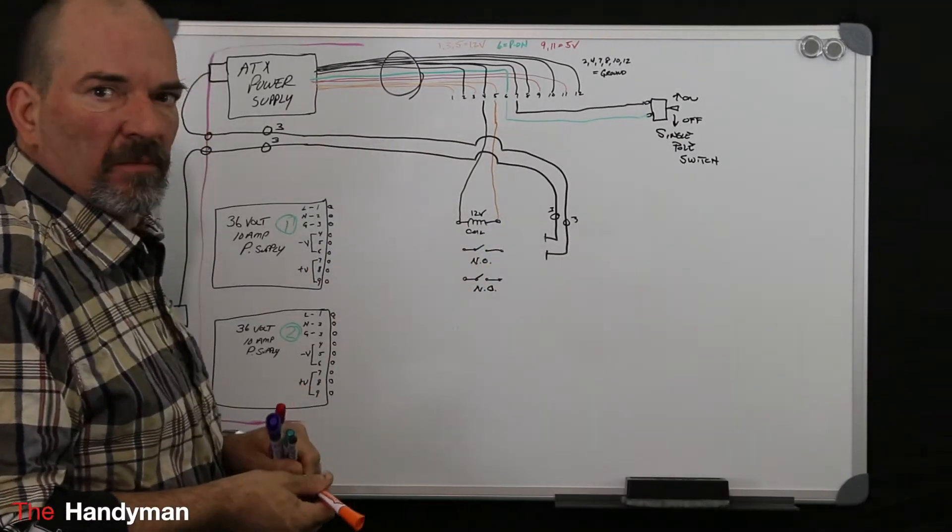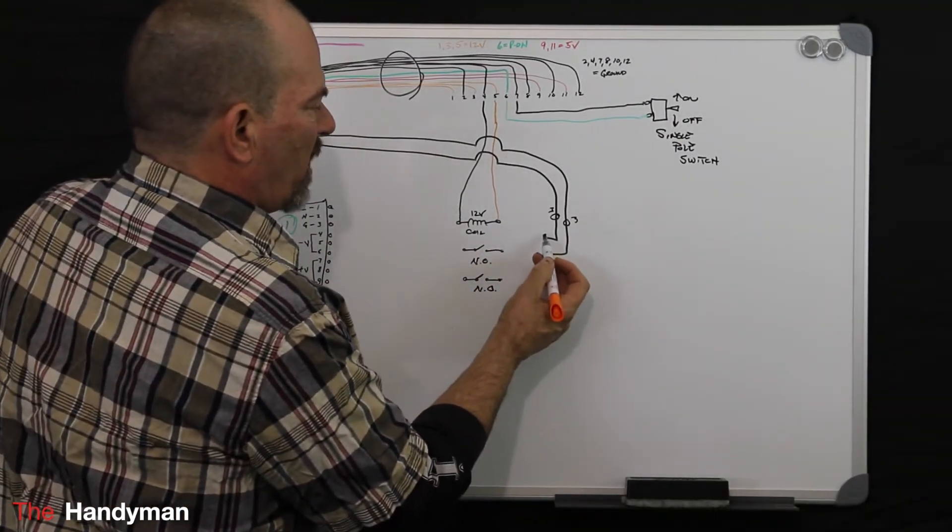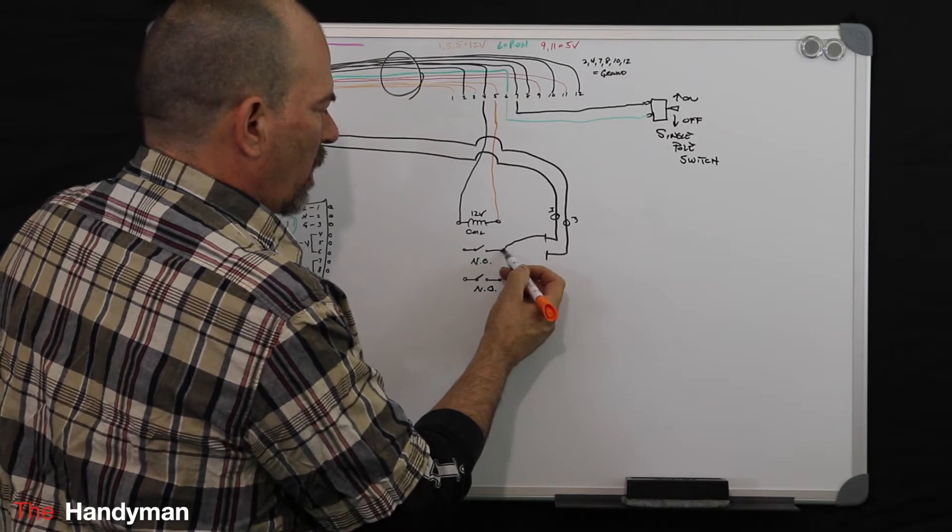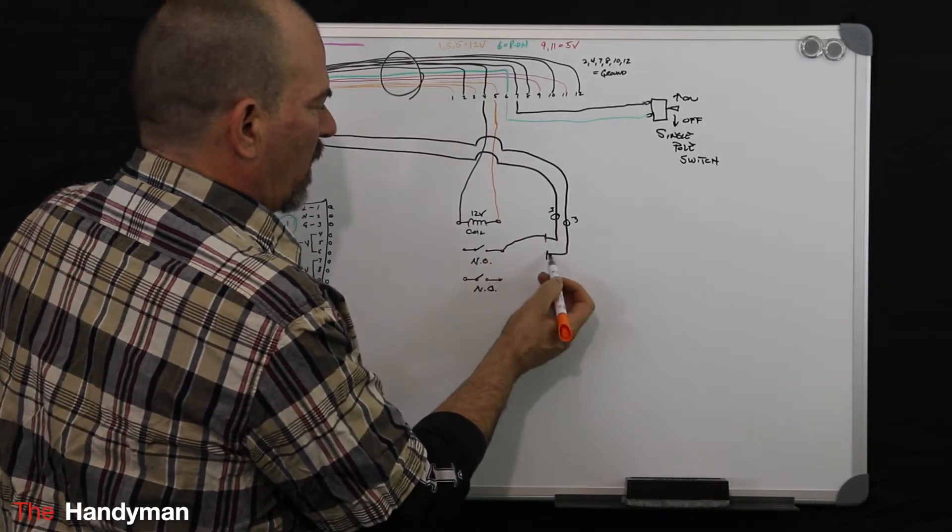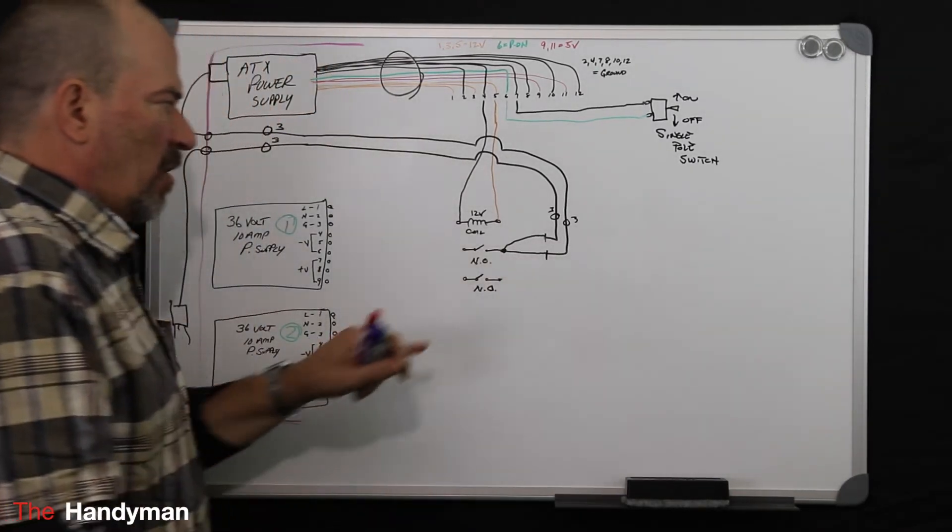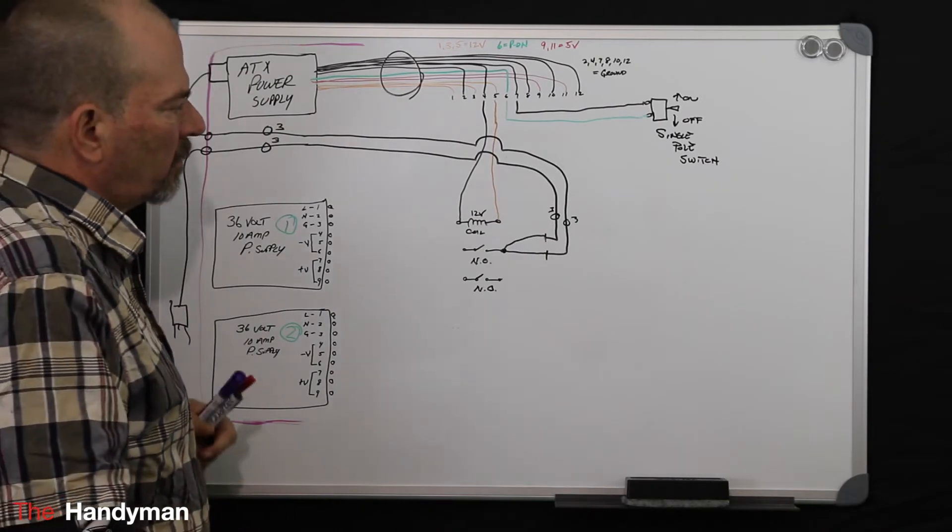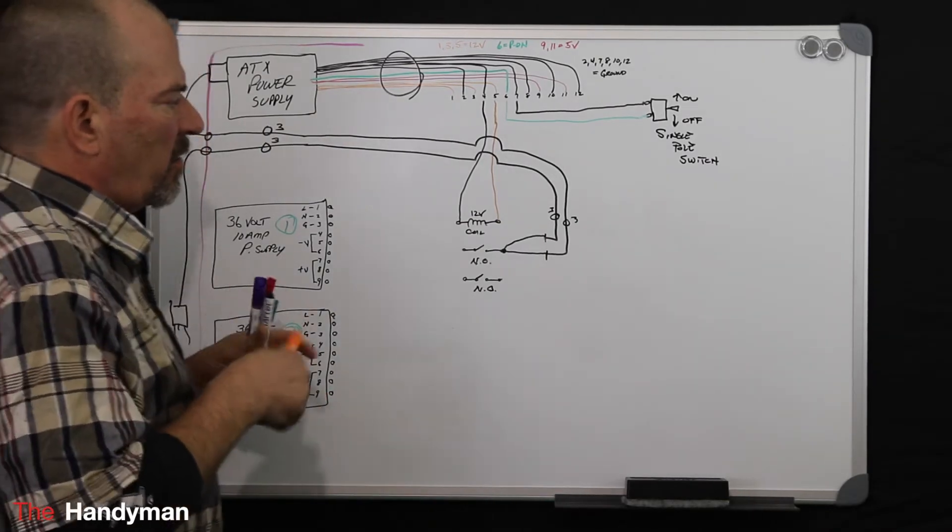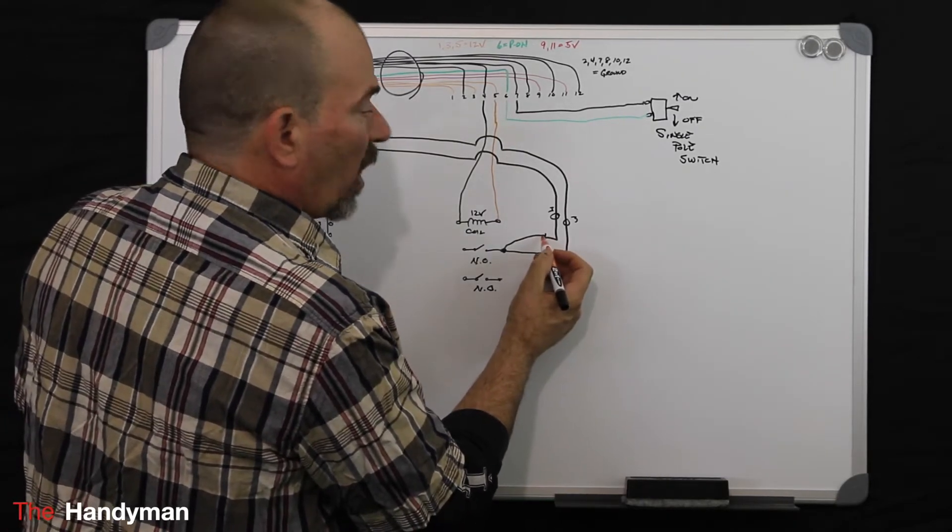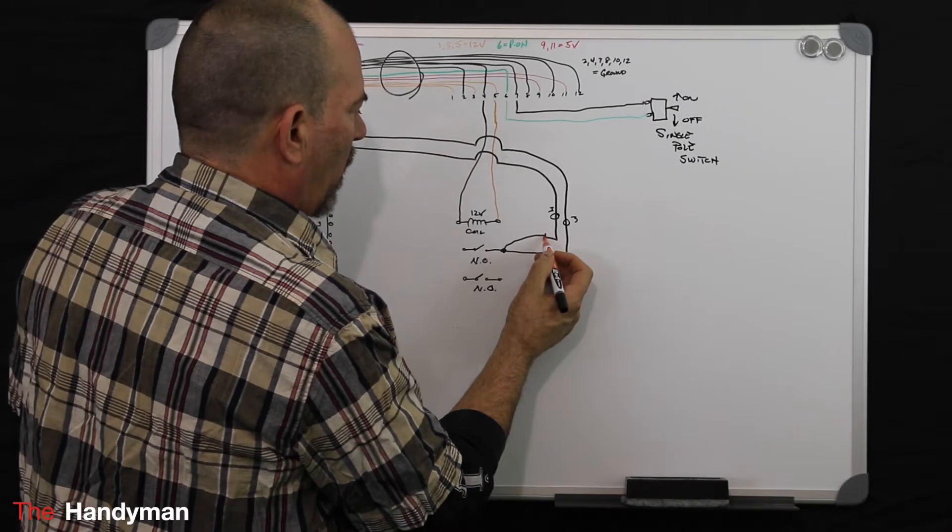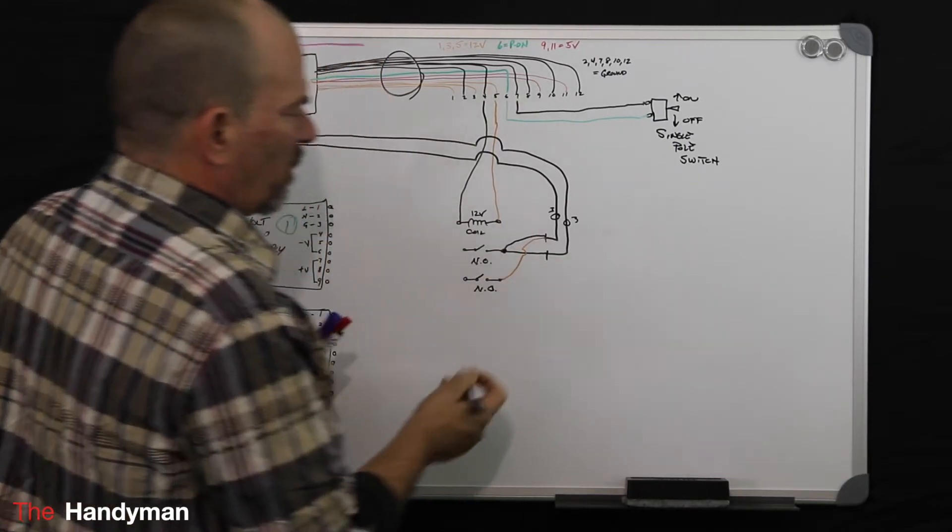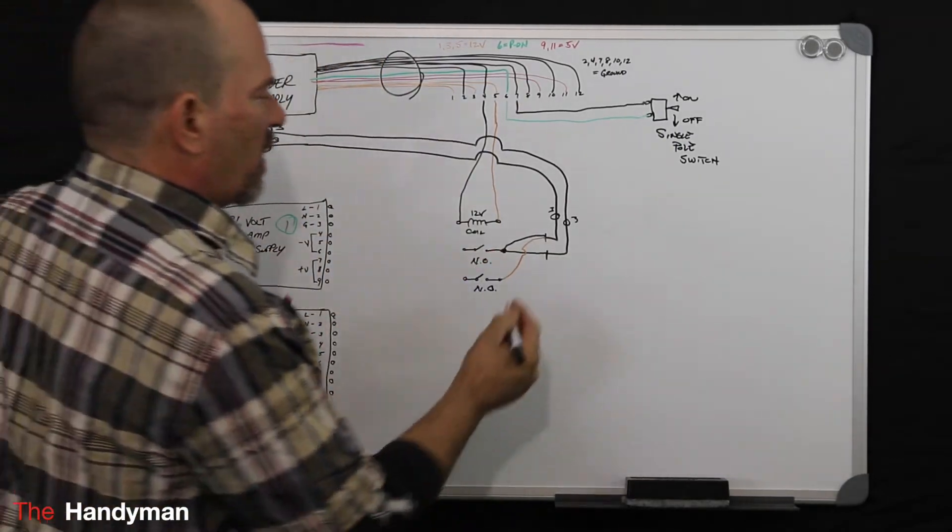So then what you're going to do is take your black wires out of each one of these cables, which is your hot, and you're going to run them in parallel to one side of your normally open contacts. Then in these cables you're going to have your neutrals, which we're going to represent with orange because I don't have white to write on white. You take your neutral out of each cable and you'll run that to another set of normally open contacts.